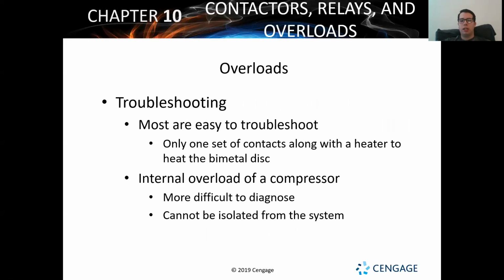So, troubleshooting overloads, again, like I said, most are easy to troubleshoot, especially fuses. You're just checking for continuity. That's it. Most of these overloads, you're just checking to make sure, okay, power path load. That is the most basic, the most common way, the easiest way to boil down all of electrical, all right? And with an overload device, it's part of the path section. So we got our power, that's coming from our breaker panel, that's coming from our power plant, that's coming from our power line, all right?